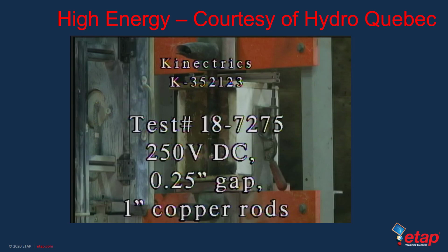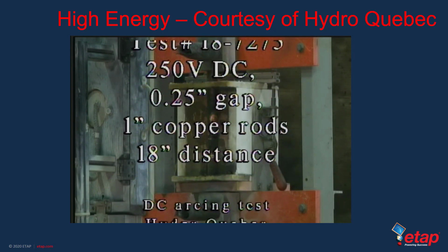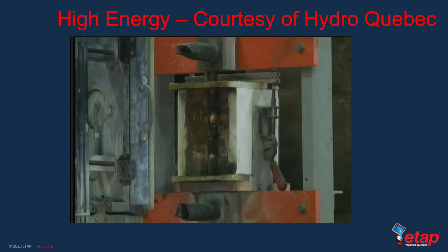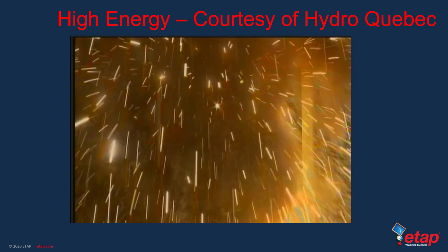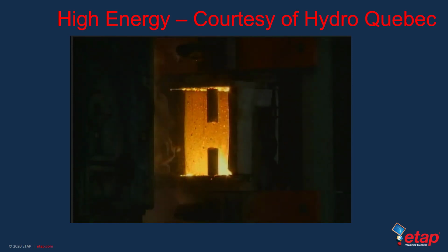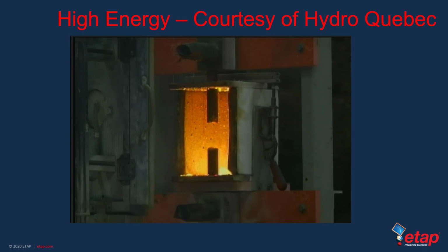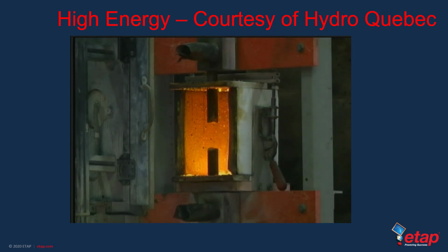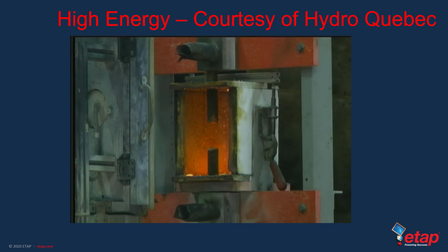This is a test that was set up with a higher voltage, approximately 260 volts DC, and a much higher current. In this case, we have 20,000 amps of available DC short circuit. Notice that we can observe almost twice as much shrapnel and also erosion of the actual copper conductors. The duration of this test is about 750 milliseconds. As we can see, the erosion rate of the conductors is significantly higher, and also the amount of shrapnel and incident energy increased significantly. This, of course, is a factor of the higher short circuit current that we have available.